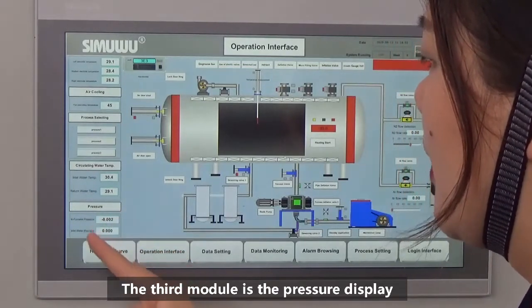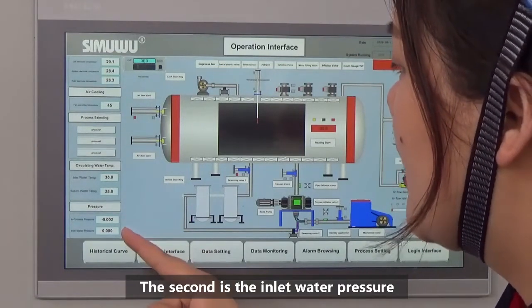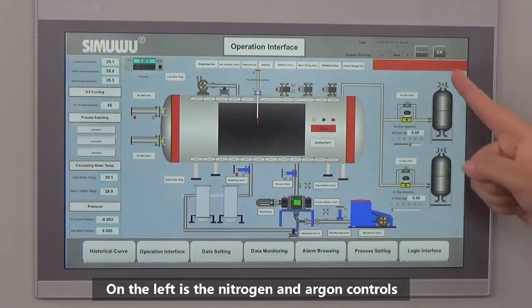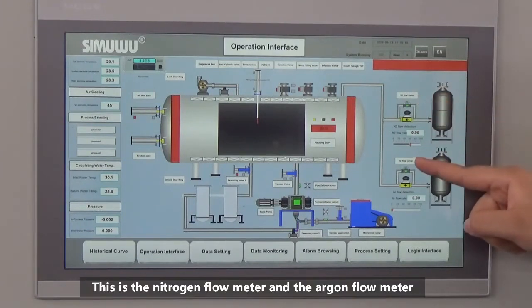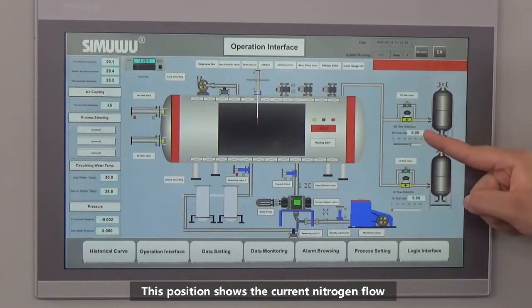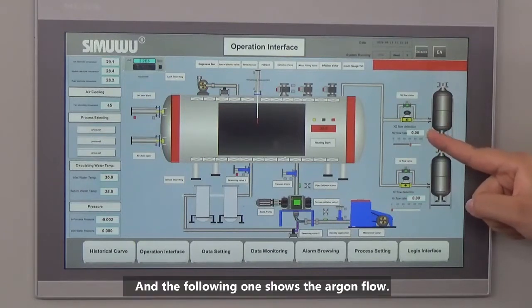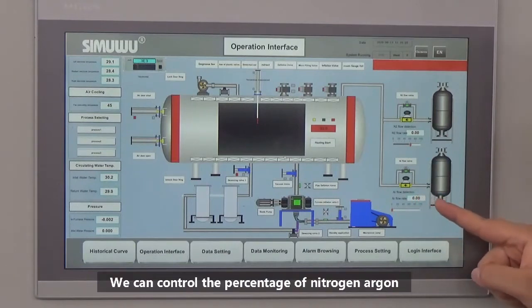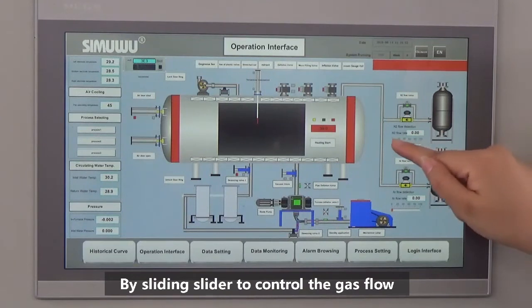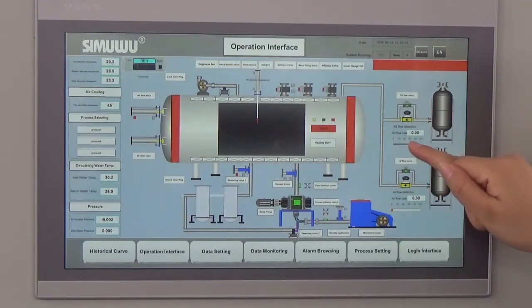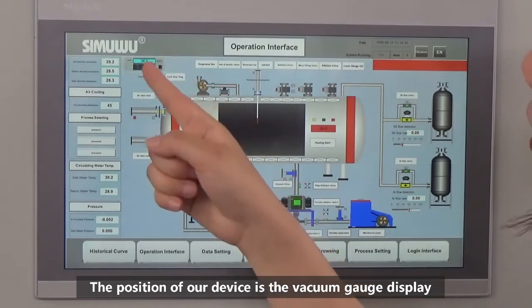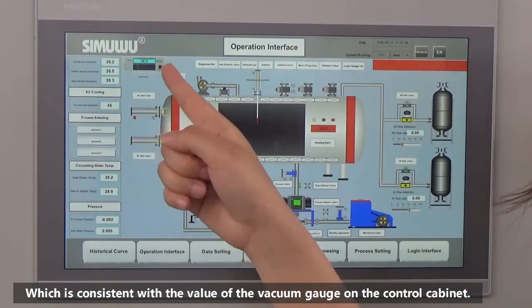The third module is the pressure display. The first value is furnace pressure and the second is inlet water pressure. On the left are nitrogen and argon controls, showing the nitrogen flow meter and argon flow meter. This position shows the current nitrogen flow and the following one shows the argon flow. We can control the percentage of nitrogen and argon by sliding the slider to adjust the gas flow. This position shows the vacuum gauge display, which is consistent with the vacuum gauge on the control cabinet.